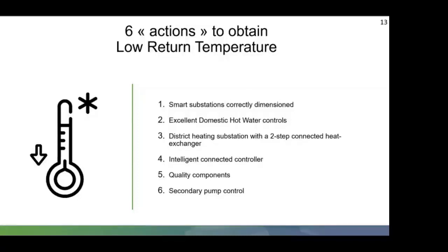stations that we provide. By using intelligent control, there is more flexibility through monitoring. This enables management of the substation and adjustments without affecting the comfort levels, and increases efficiency. So again, if you look at the way it's controlled properly, if you use some smart controllers, if you look at maybe outside temperatures, inside temperatures, knocking down the flow a couple of degrees but still giving comfortable heat within the building, there's ways of doing things.